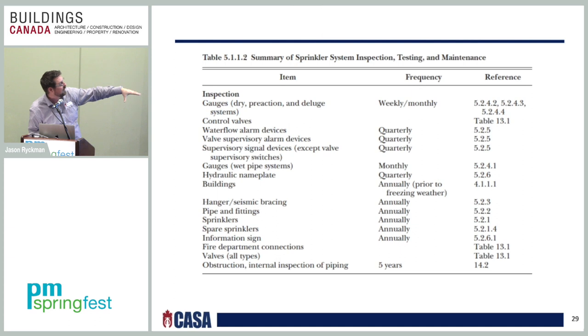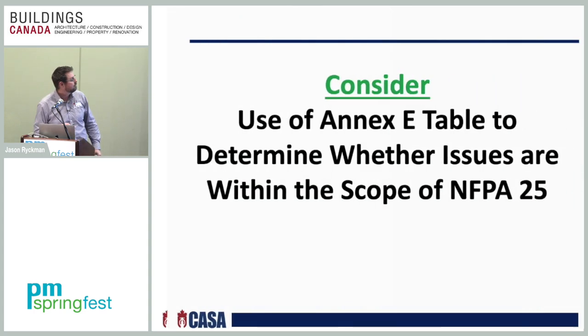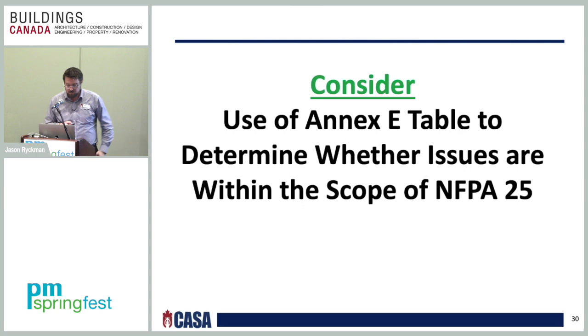Some more examples of the frequencies. So it gives you weeklies, monthlies, quarterlies, annuals, and then even every 5 years, an obstruction internal inspection of the piping has to be done every 5 years if using NFPA 25. That's per 14.2. Here's another table, a table used in Annex E, to determine whether issues are within the scope of NFPA 25.